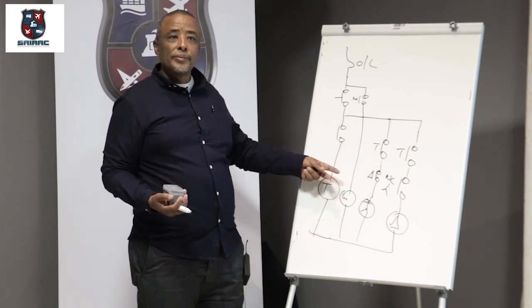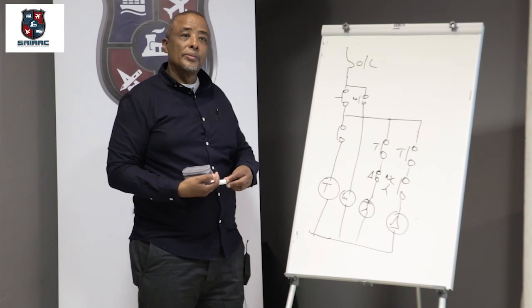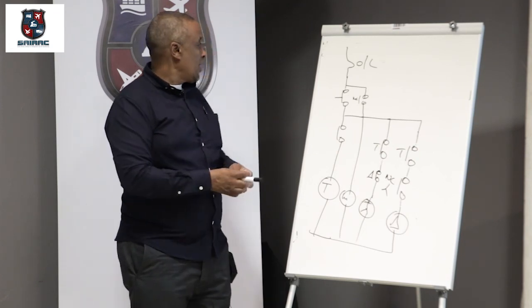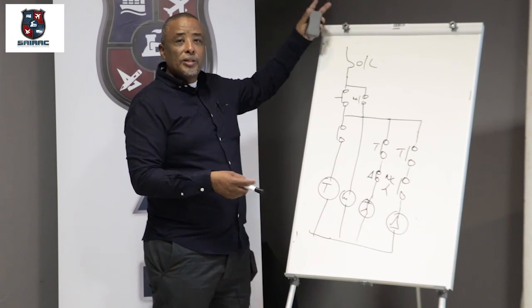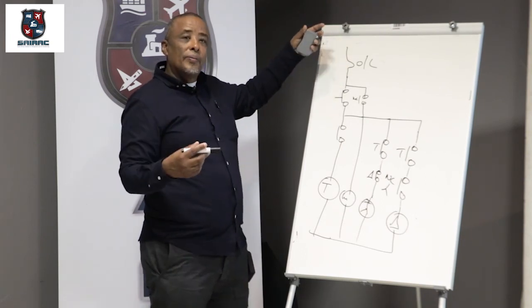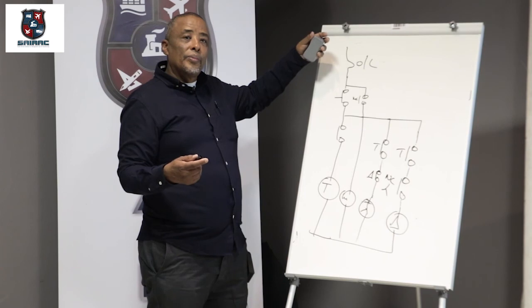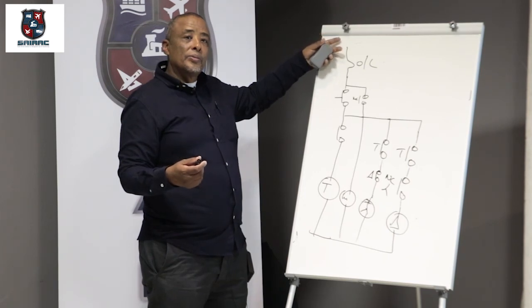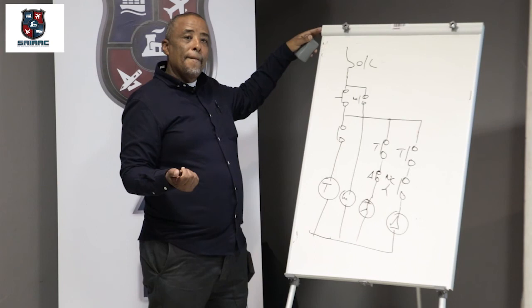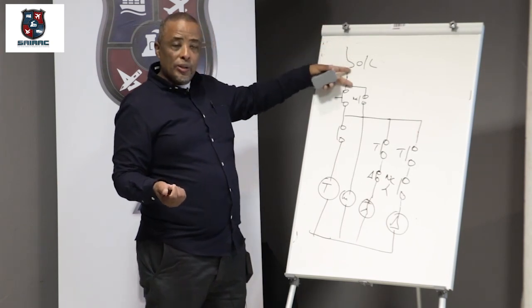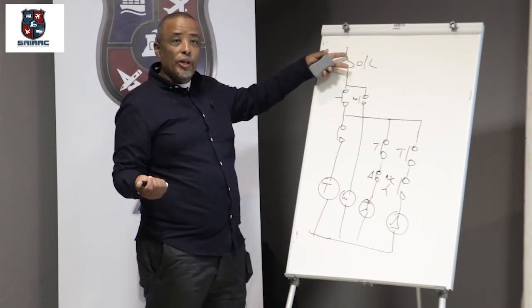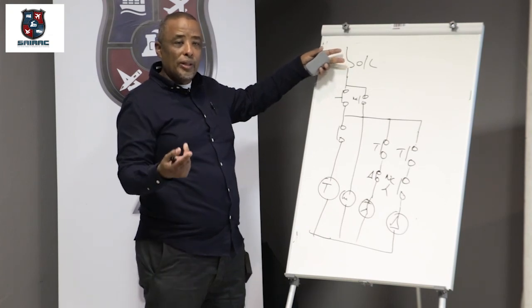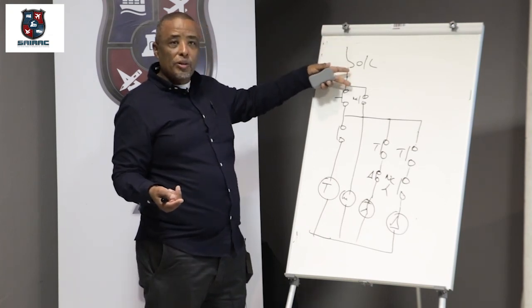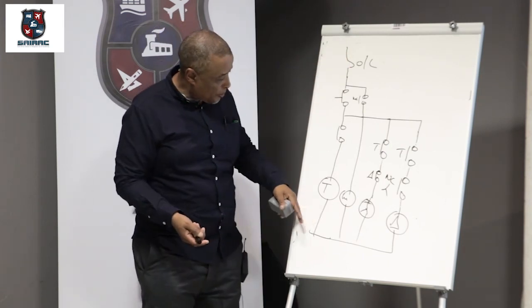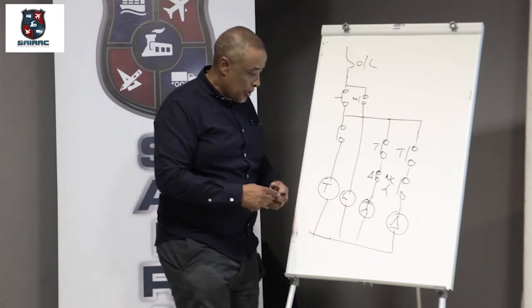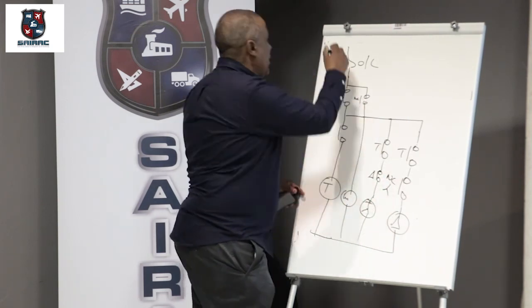Where would you use, because in our field we have thermostats, normally... You can add it anywhere. You can add it in series, as long as it's in series. Your emergency stop. Yeah, but it needs to monitor first through the controls. So there's a signal coming from somewhere. Okay. Where would you input that signal? Anywhere in series with this. It will normally close, yeah. Thermocouples, that type of thing. They all will be in series with the control circuits. You can put it there. You can even put it wherever you want it. You can put it even here. That's your line 1, let's say.